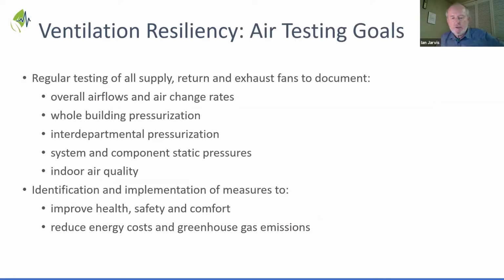So when we do air testing, what is the framework? What are the goals? What are the objectives? What's the point that we would like everybody to get to after this webinar? What is the action we'd like you to take? So one is a regular testing schedule around all significant supply, return, and exhaust fans. So when they've been measured, and not just at the airflow level, but at the static pressure level, at the observation level, at the inspection level, you can know with confidence what your overall airflows are and what kind of air change rates you have throughout the hospital.